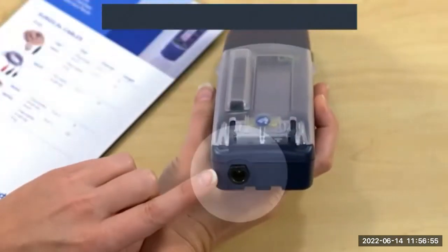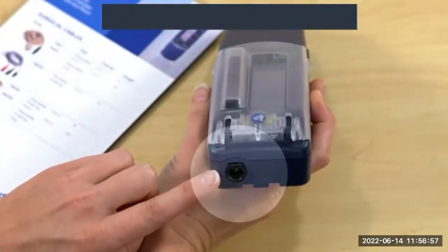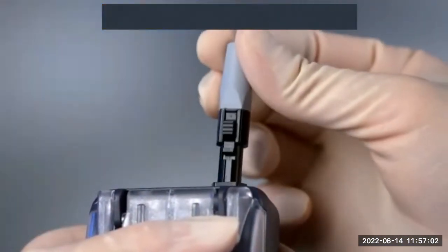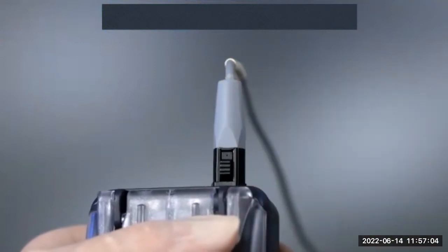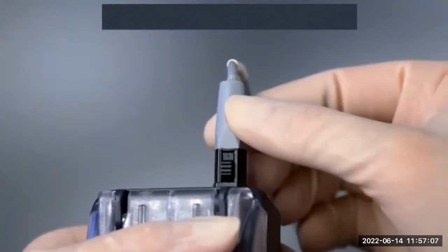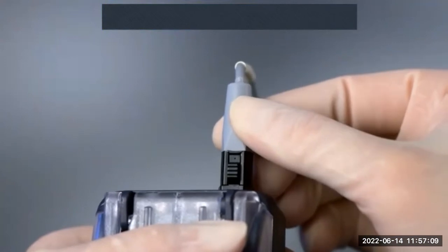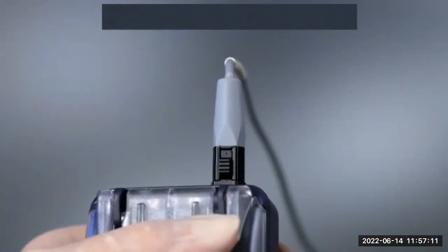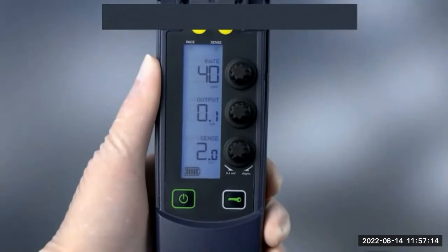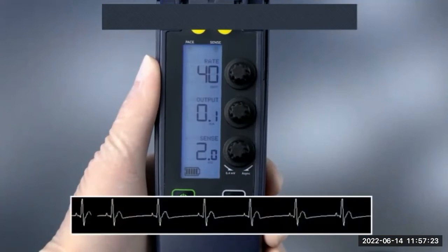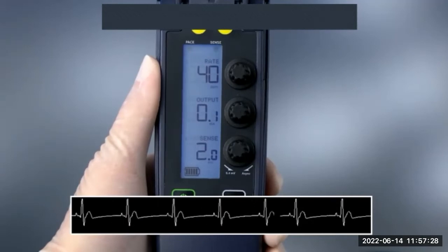Plug the pacing cable into the socket located on the connector block on top of the temporary pacemaker. Verify that the cable end clicks when it is inserted into the temporary pacemaker connection. The audible click signifies that the plug is completely inserted into the receptacle. Note the sense indicator is flashing, which means the device is detecting the R wave. In other words, the R wave is at least 2 millivolts. Monitor the patient's ECG to ensure the sense indicator matches the device lights.